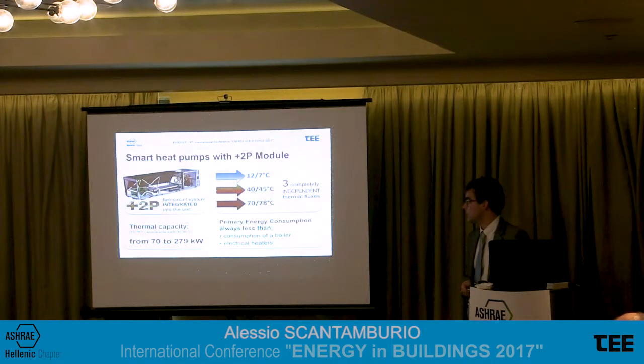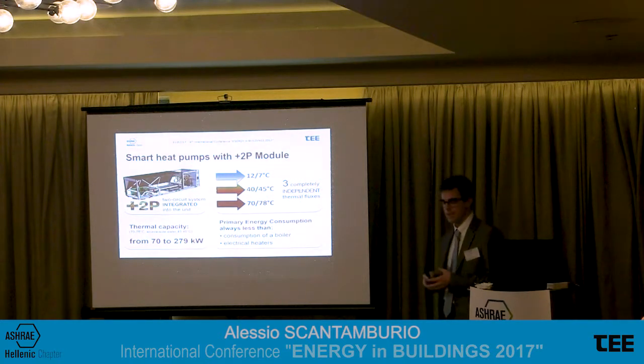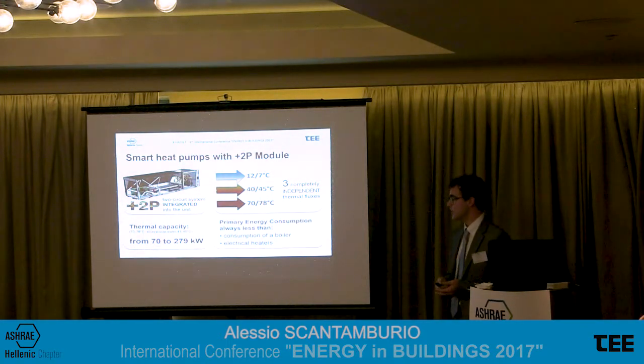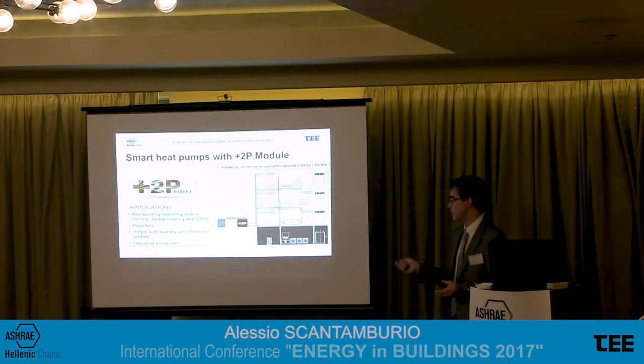But there's another technology which works in cascade with the main 4-pipe unit, which allows us to produce very hot water, up to 78 degrees. So by coupling this additional water-to-water heat pump with the main 4-pipe unit, we are able to set up a cascade system and deliver 3 independent thermal fluxes. For example, this could be an application where we have comfort cooling, comfort heating, and also domestic hot water, laundry services, and so on. So typical for a hotel application, for example.